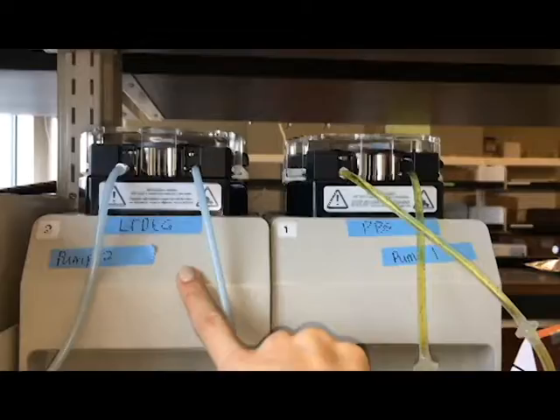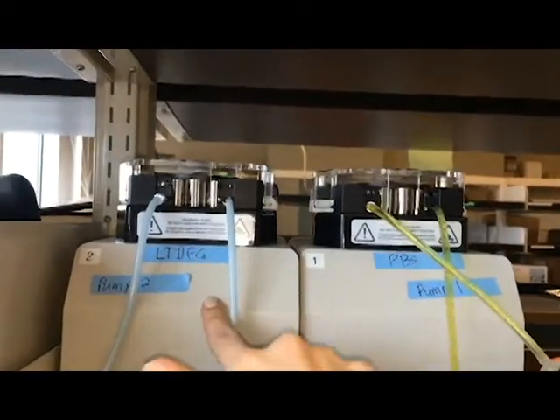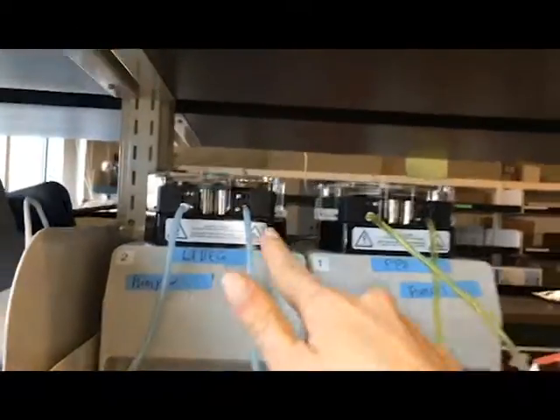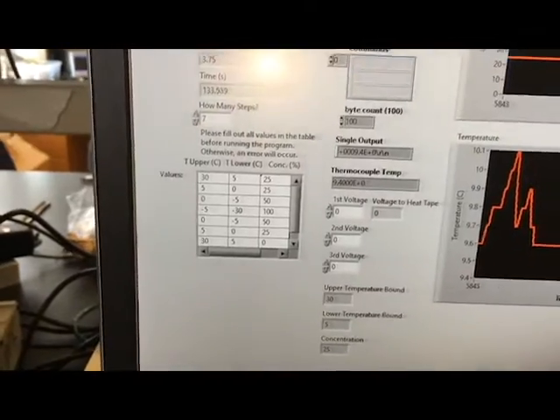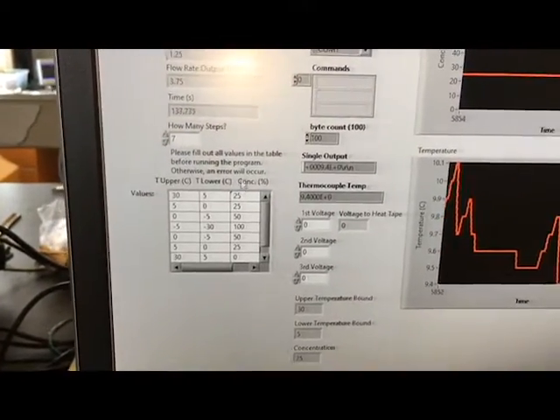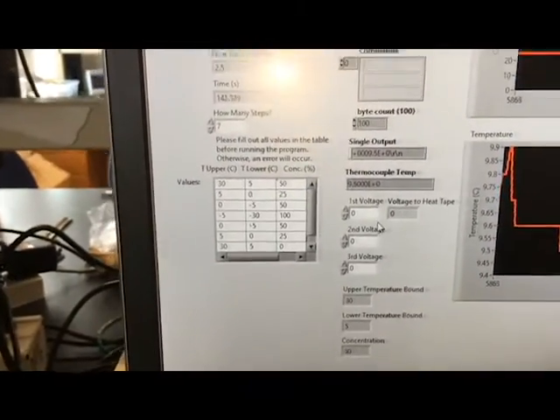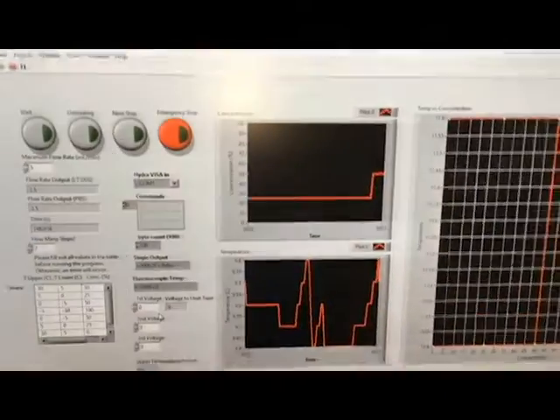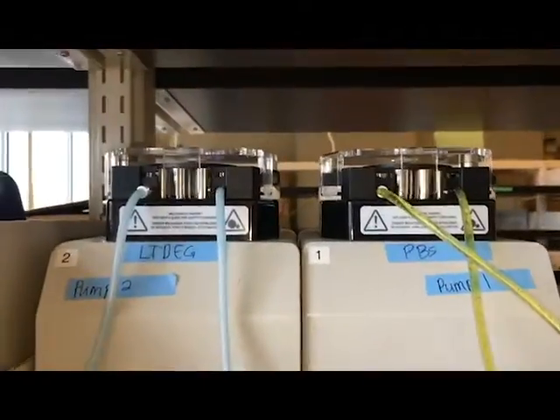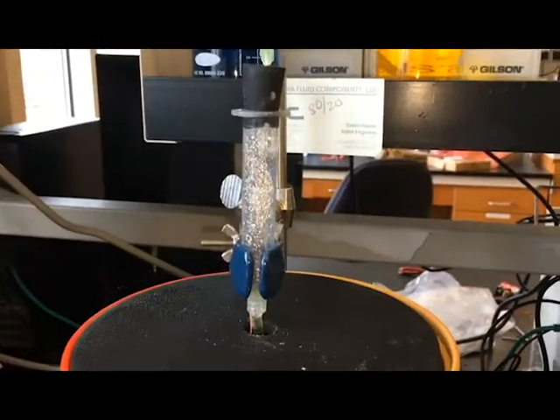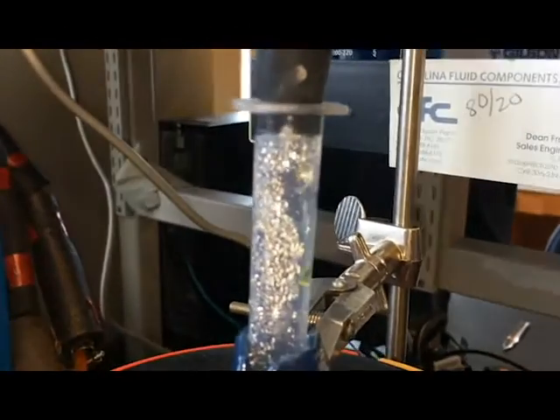While the device is being used to load and unload the vitrification solution, the concentration will change automatically in response to the temperature of the fluid entering the cell chamber. If you want to increase the concentration to 50%, you can see that there is a jump in the concentration curve. And if we go here to the pumps, you can see that they are both flowing at the exact same rate. And if we show the bubble trap, we can see that the blue and yellow drops are falling at the same rate from the trap.